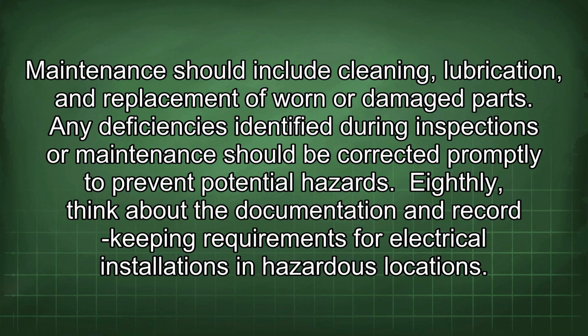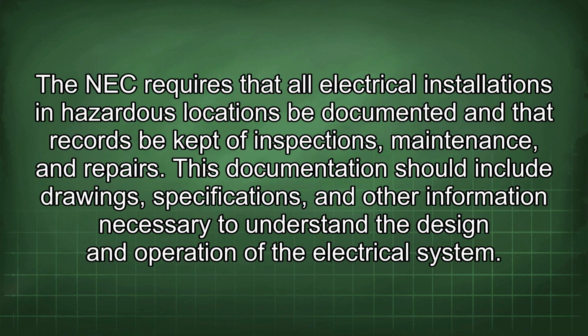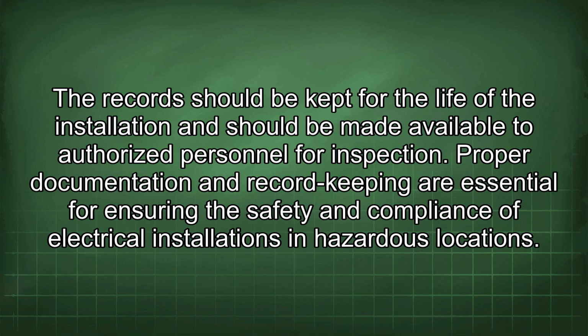Eighthly, think about the documentation and record-keeping requirements for electrical installations in hazardous locations. The NEC requires that all electrical installations in hazardous locations be documented and that records be kept of inspections, maintenance, and repairs. This documentation should include drawings, specifications, and other information necessary to understand the design and operation of the electrical system. The record should be kept for the life of the installation and should be made available to authorized personnel for inspection. Proper documentation and record keeping are essential for ensuring the safety and compliance of electrical installations in hazardous locations.